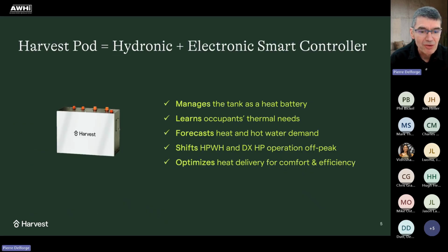So a little more about the controller. I mentioned it's a hydronic controller, but most importantly, it's a smart controller, and that's what makes the system work. The cloud-connected electronics controller in the pod is what turns a regular water heating tank, humble 100-year-old technology, into a smart thermal battery by modeling its stratification profile, and we have 2-gallon layers, and we know the temperature of every layer at any point in time, and we recalibrate it constantly by measuring inputs and outputs. And that knowledge of the state of charge is the basis for all the load shifting, the charging, the discharging, the entire algorithm.